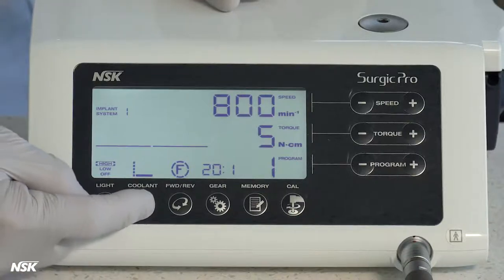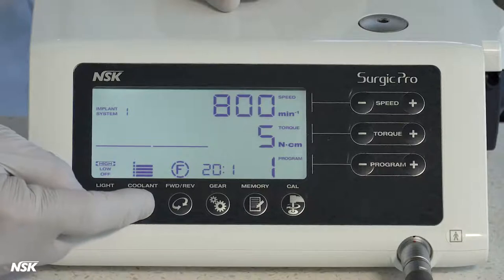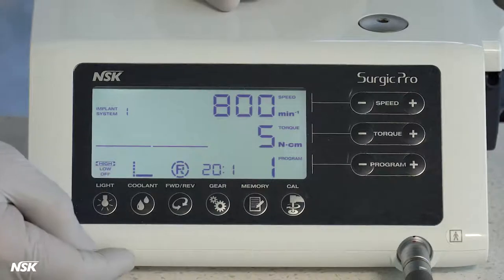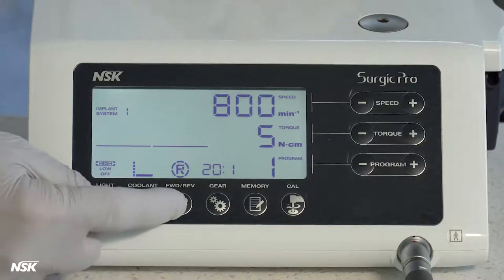Coolant flow button adjusts the level of coolant and can be set up to six different levels, which includes no water flow at all. Forward reverse button changes the rotational direction of the micromotor.